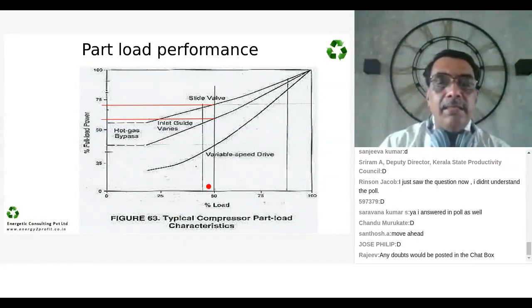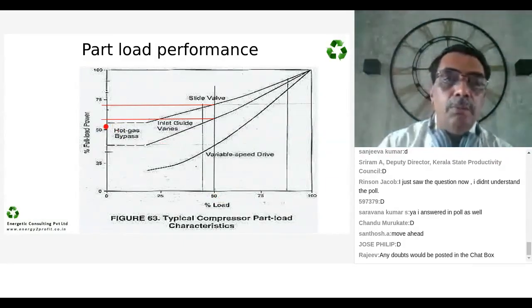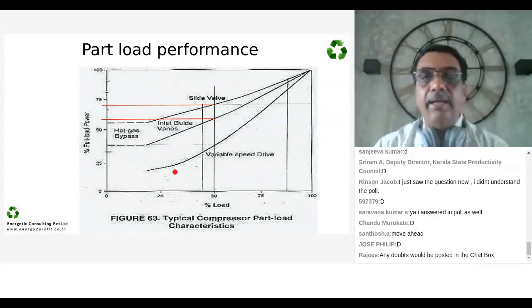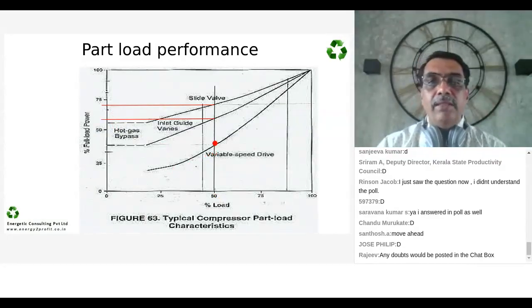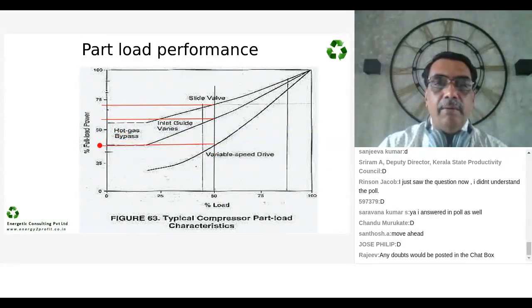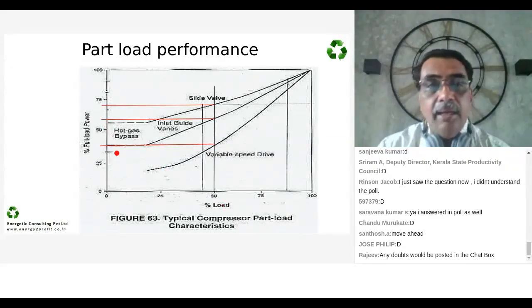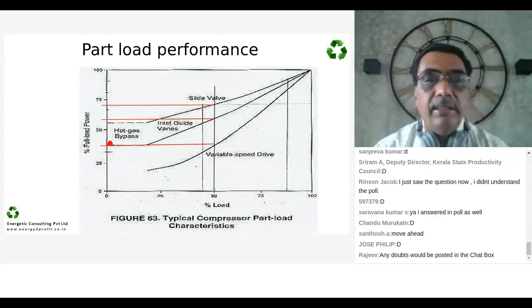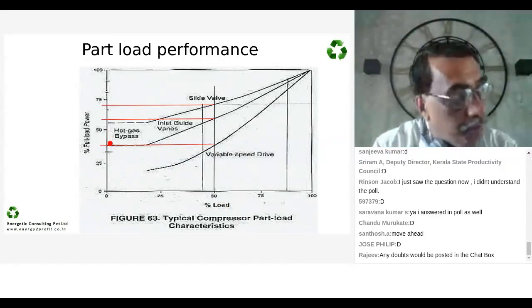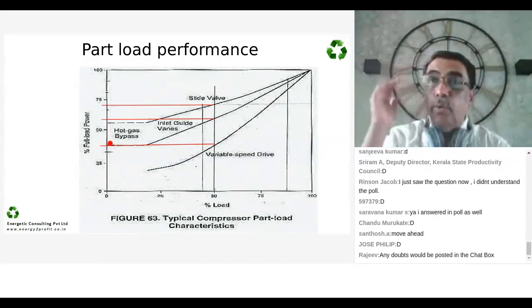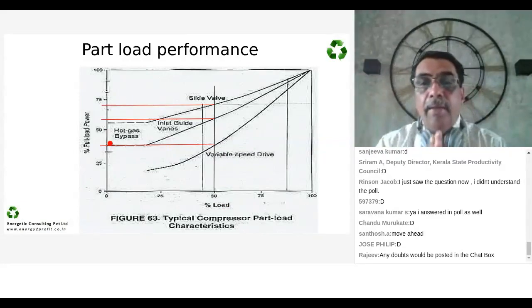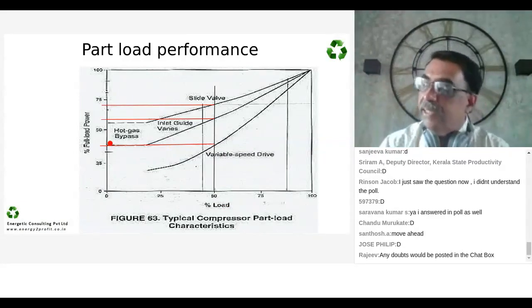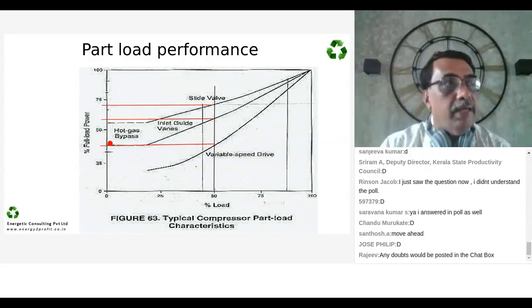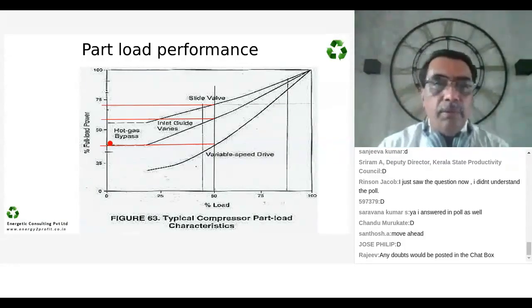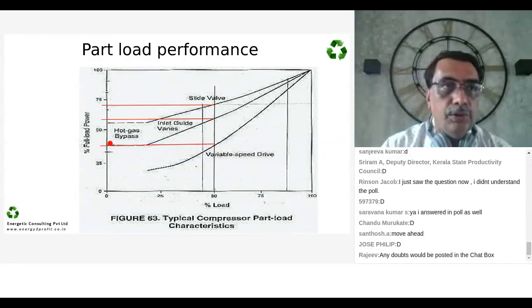It means at 50% load, it will consume around 55% energy. How does variable speed work? It actually works at 50%, it will consume lesser energy than 50% because it is reducing the pressure ratio and the quantity together. And therefore, you have centrifugal compressors which show a much better efficiency in terms of COP at part loads.